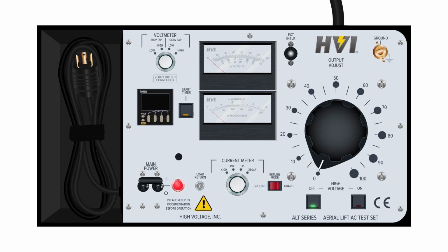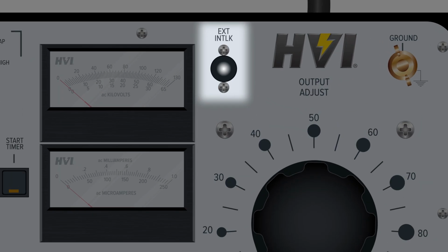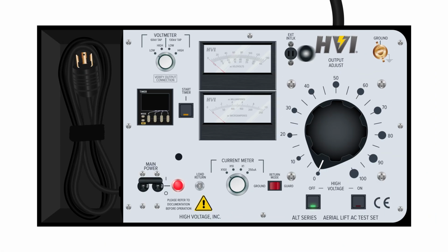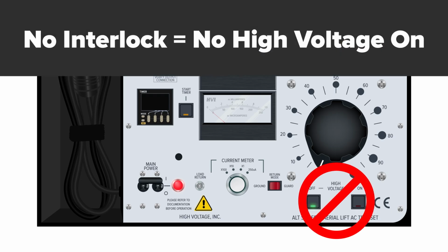The external interlock is located at the top of the control panel, immediately to the right of the voltmeter. When the interlock key is not secured into the external interlock, the high-voltage circuit will not function by design, even if the output dial is set to 0.